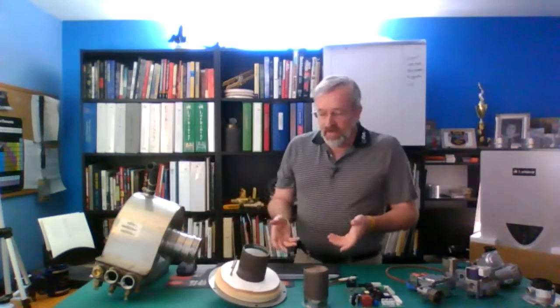We've talked about the differences in the gas train, where they're very similar and yet a little bit different, but it's negative regulation. We're using the orifices and the venturis on both to create that combustion. But let's take a look at our burners. I have a burner right here. This is from a WH, the fire tube design. This burner here is a KBN water tube design. Very similar, with an Alcromesh coating on the outside of that stainless steel burner tube.